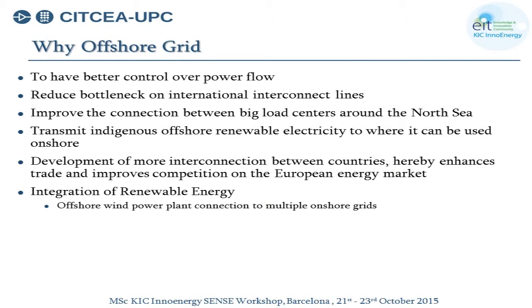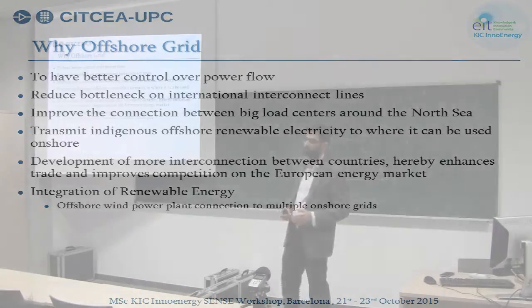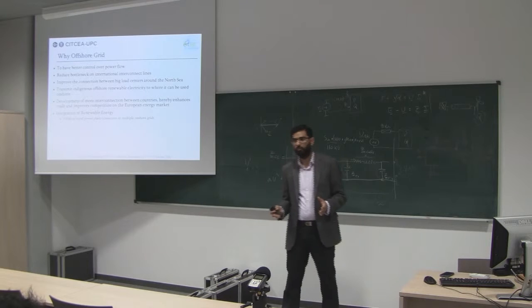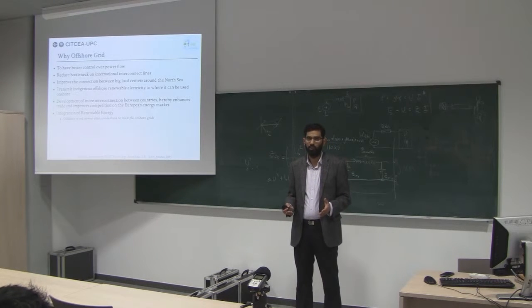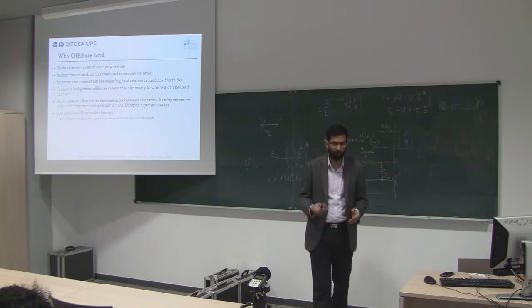The problem with the phase shifter transformer is if you have two countries connecting together, you have to synchronize the phase angle of the reference voltage of both countries, and create the angle difference to control the power flow, which is complicated and doesn't give much flexibility. If we have an HVDC system instead, we isolate the system and can control our power flow more easily compared to an AC system.